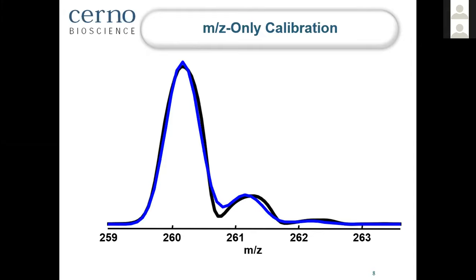However, in order to keep all the information in the profile mode and analyze in the profile mode, we see that the traditional conventional calibration is not sufficient. It leaves a lot of spectral error in the rest of the spectral region. And that spectral error is on the order of 5 to 10%, perhaps more than sufficient to obscure or destroy the difference we want to see between one elemental composition and another. So that would not allow us to determine elemental composition by using the conventional mass spec calibration approach.